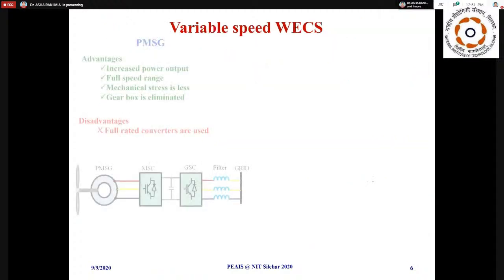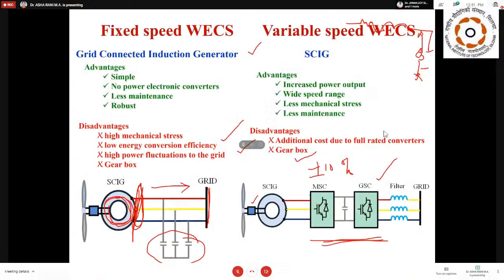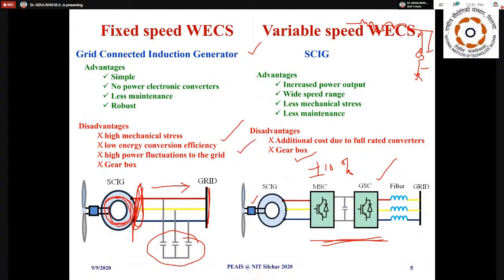Now coming to the variable speed wind energy conversion system, one configuration is the SCIG with a back-to-back configuration, but this has a major disadvantage. When SCIG is directly connected to the grid through this configuration, it uses two full converters. These generators are individually generating power in the range of megawatts, so for handling that much power and thousands of amperes of current, the converters used should be full converters, which means the cost is huge. So for extracting only plus or minus 10% of power with such costly converters is not a great idea. There are actual disadvantages to this scheme.